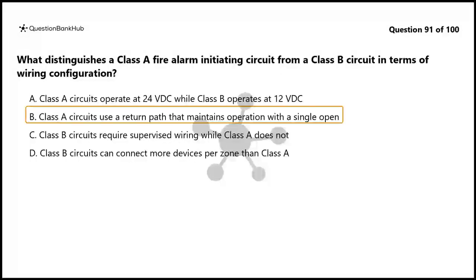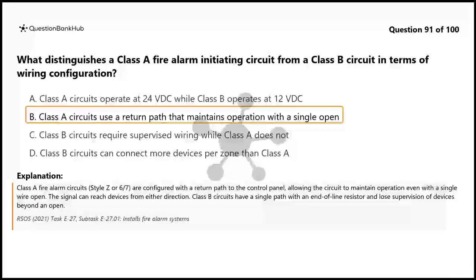The correct answer is B. Class A circuits use a return path that maintains operation with a single open. Class A fire alarm circuits, style Z or 6-7, are configured with a return path to the control panel, allowing the circuit to maintain operation even with a single wire open. The signal can reach devices from either direction. Class B circuits have a single path with an end-of-line resistor and lose supervision of devices beyond an open.